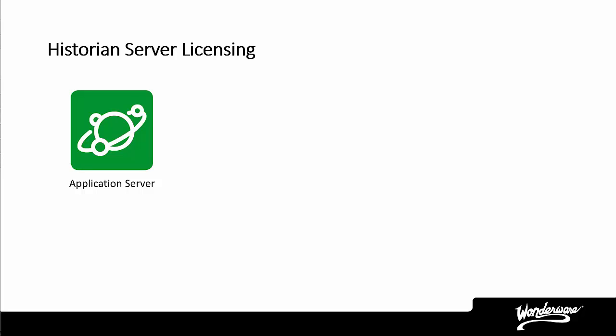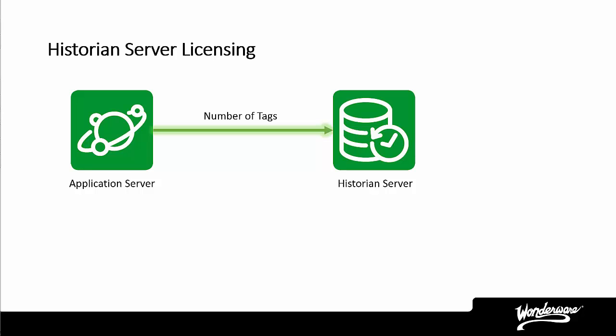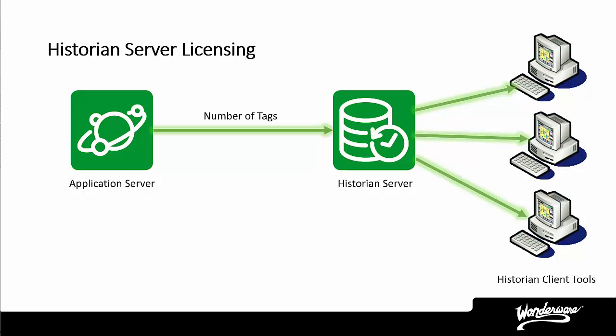The next product is the Historian Server. In a Wonderware System Platform application, all configuration is contained in the Wonderware Application Server. You can enable any variable to be historized to the Wonderware Historian. When this is done, the Wonderware Historian configuration for the variable and its data is pushed from the Application Server to the Historian. The Wonderware Historian is licensed based on the variables configured in it — Wonderware calls these variables tags. When you enable a variable in the Application Server to historize its data, this adds one tag to the Wonderware Historian license count. The Historian stores data so that other computers can access it.